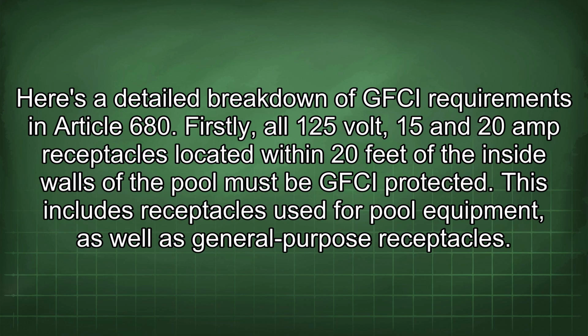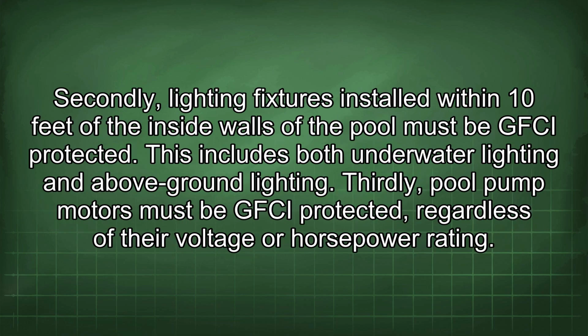Firstly, all 125-volt, 15 and 20 amp receptacles located within 20 feet of the inside walls of the pool must be GFCI protected. This includes receptacles used for pool equipment, as well as general-purpose receptacles. Secondly, lighting fixtures installed within 10 feet of the inside walls of the pool must be GFCI protected. This includes both underwater lighting and above-ground lighting.